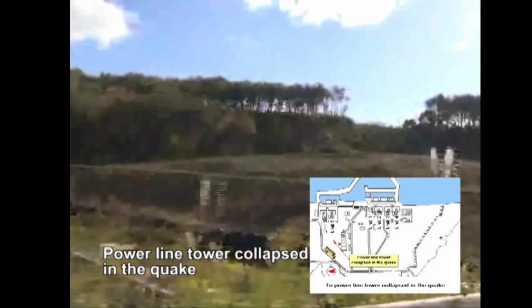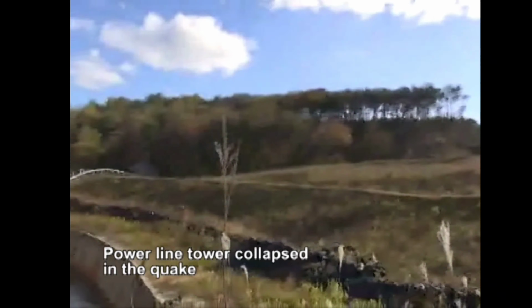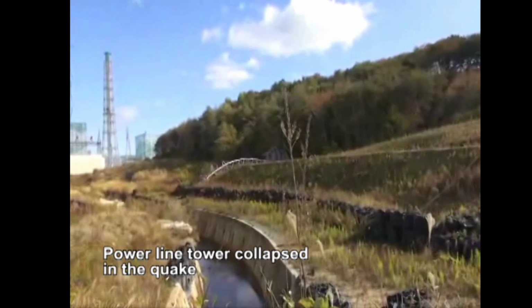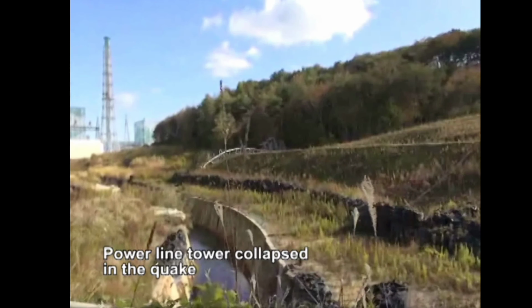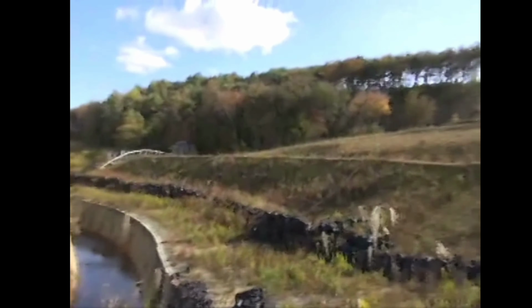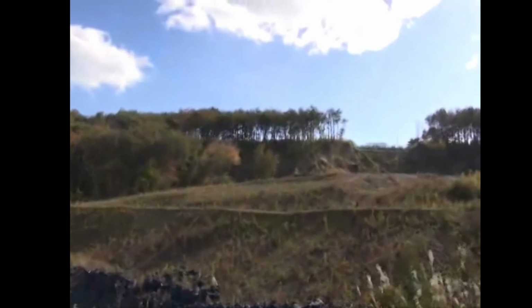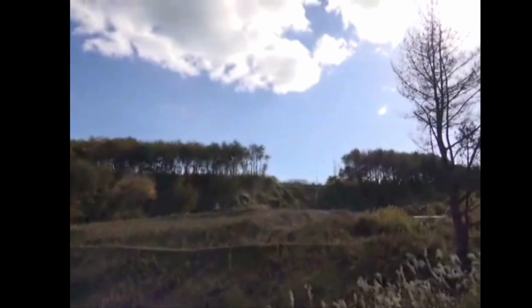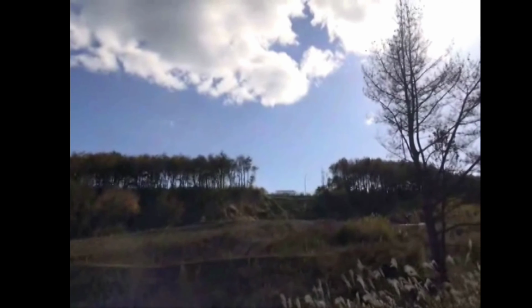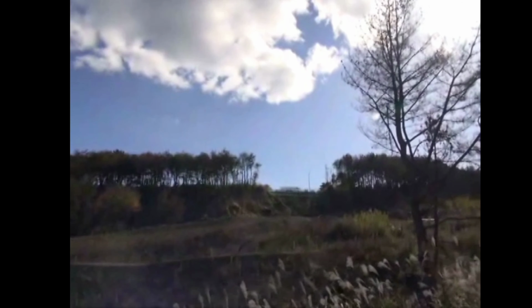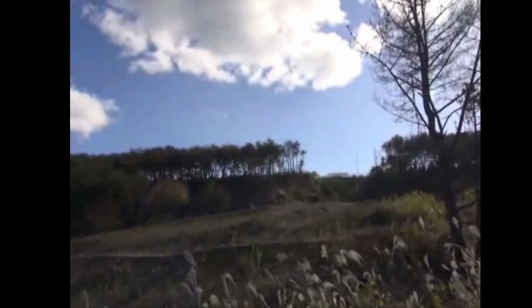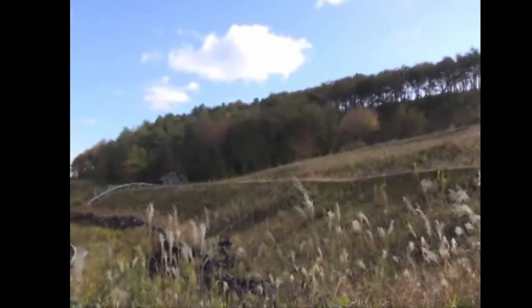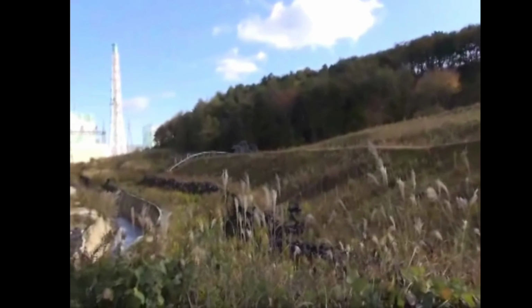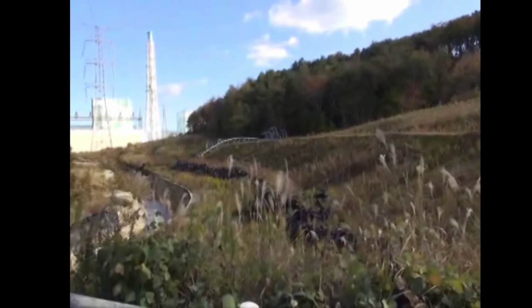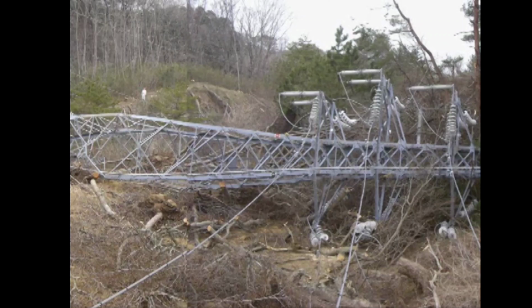Units 5 and 6 were receiving external power through two lines of the 66 kilovolt Yonomori line. A power line tower fell over due to a collapse of a large embankment in the surrounding area after the earthquake, which led to a loss of off-site power supply. Now the two lines of the 500 kilovolt Futaba line originally used for power transmission are being used for providing power to the two units. The power is supplied to these lines from Shin Fukushima substation located 10 kilometers from the power station.